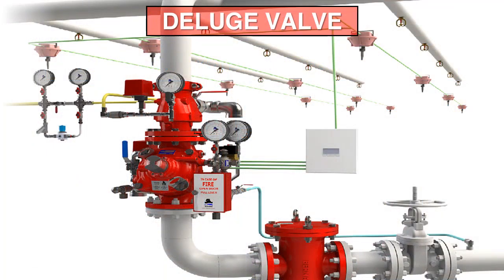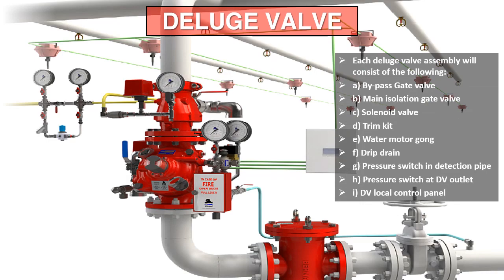We will see the major components of the deluge valve and its working principle. The major components of a deluge valve assembly are: bypass gate valve, main isolation gate valve, solenoid valve, trim kit assembly, water motor gong, drip drain, pressure switch in detection pipe, pressure switch at DV outlet, and deluge valve local control panel.